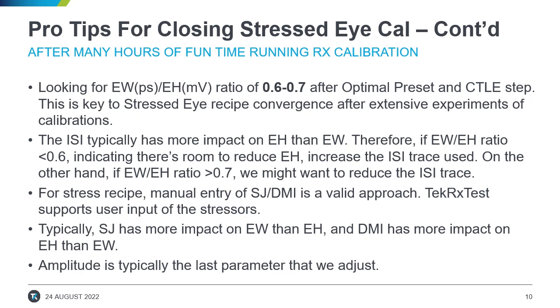And for the stress recipe, it actually allows the manual entry of SJ and DMI. That is a valid approach. And the Tektronix automation software also supports user input of these stressors. And typically, the SJ has more impact on eye width than eye height, and DMI has more impact on eye height than eye width. And amplitude is typically the last parameter that we adjust. We almost never see the need for adjusting amplitude to close the calibration.